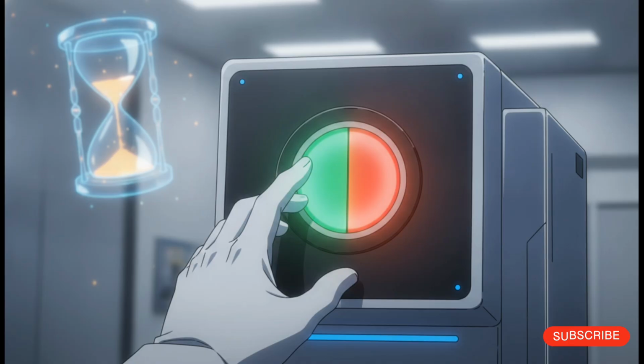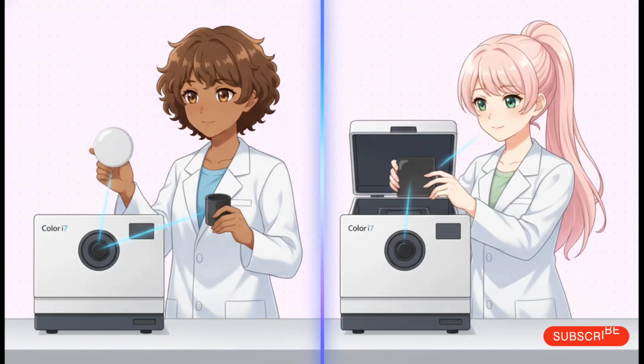Oh, and on the front status panel of your device, there's a calibrate LED. If you see that turn from green to red, well, the system is literally telling you it's time to calibrate. Now, your calibration workflow is going to differ depending on what you're actually measuring. For a standard reflectance calibration, you'll use your software interface to launch the process, and it'll prompt you to present your round white calibration tile, followed directly by the black trap.